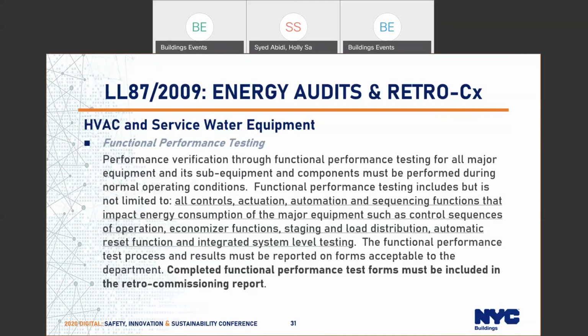Functional performance testing is performance verification of all major equipment and its sub-equipment and components. Functional performance testing includes, but is not limited to, all controls, actuation, automation, and sequencing functions that impact energy consumption of the major equipment, such as control sequence of operation, economizer functions, staging and load distribution, automatic reset functions, and integrated system level testing. Complete functional performance test forms must be included in the retro-commissioning report.